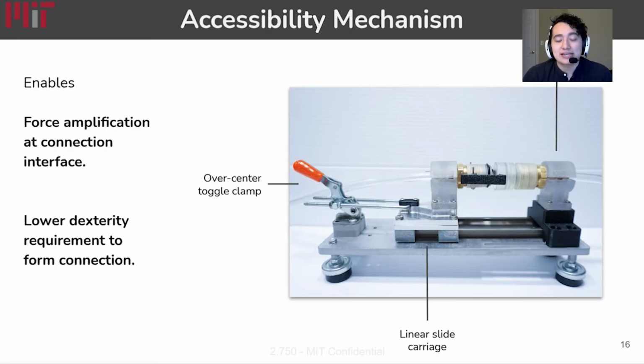The goal of our accessibility mechanism is to lower the physical requirements necessary for forming the catheter fluid connection. It does so in two ways. The first is by amplifying the force provided by the user through the toggle clamp lever and into the connection interface by 3 times. The force amplification works through the 2-bar linkage design of the over-center toggle clamp that we use to move the carriage holding the catheter terminal.